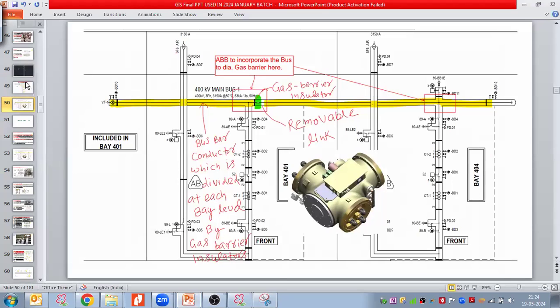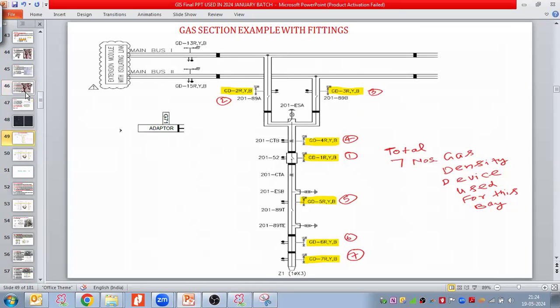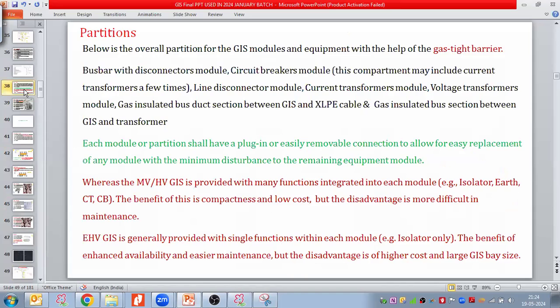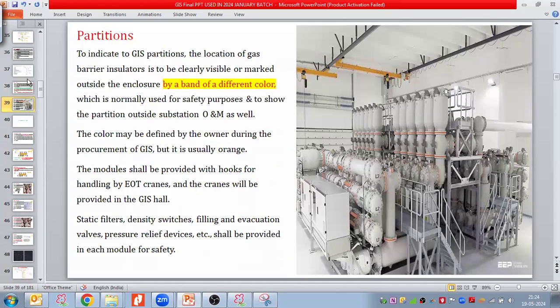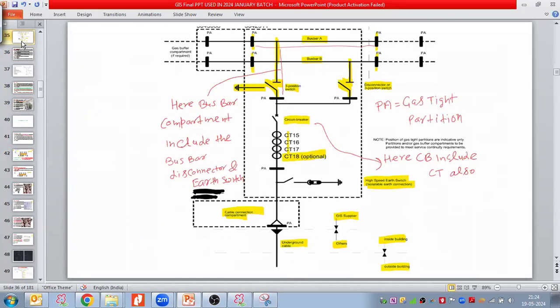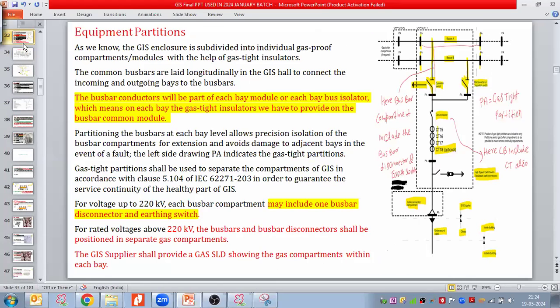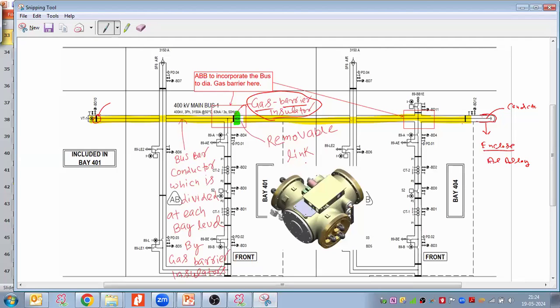Let me go to the gas partition practice. The bus bar conductor will be part of each bay module or each bay bus isolator, which means on each bay the gas tight insulator or gas barrier insulator has to be provided by the manufacturer on the bus bar common module. Taking this statement, now apply it to the drawing. See, what is the mistake here?